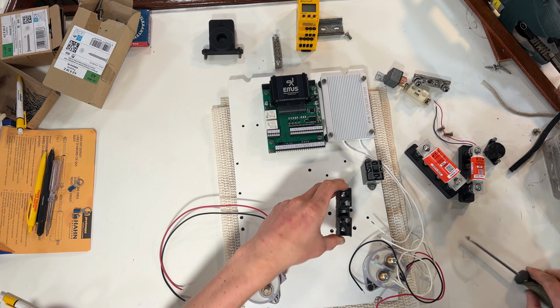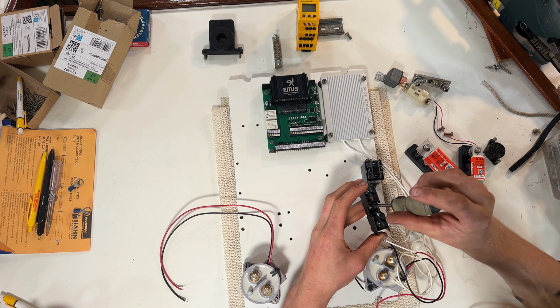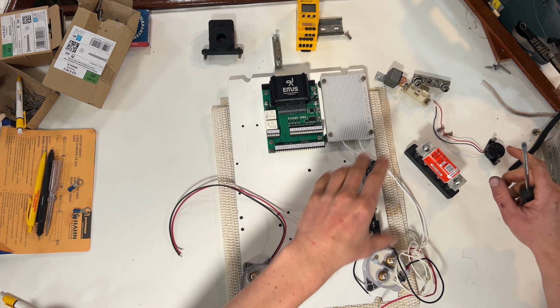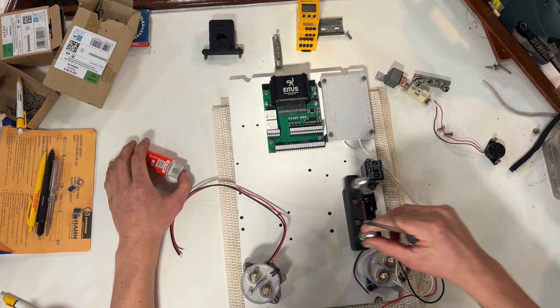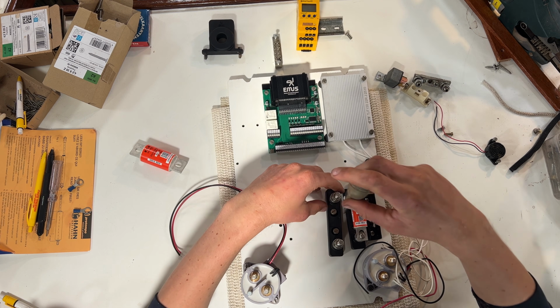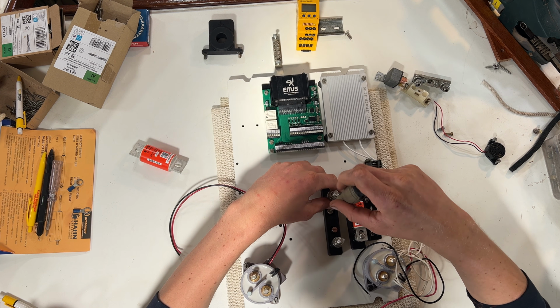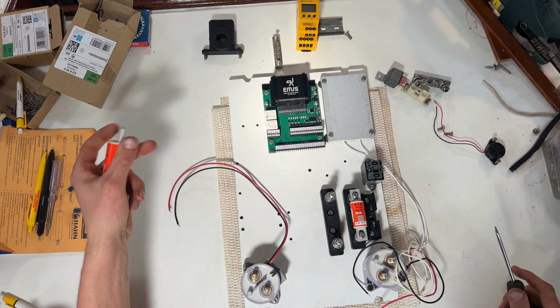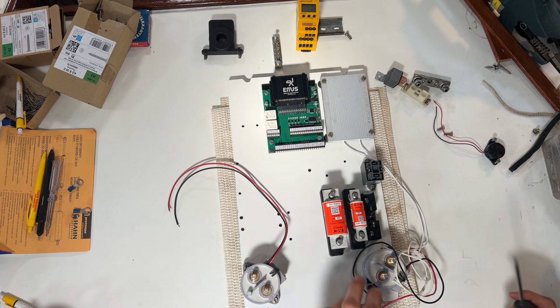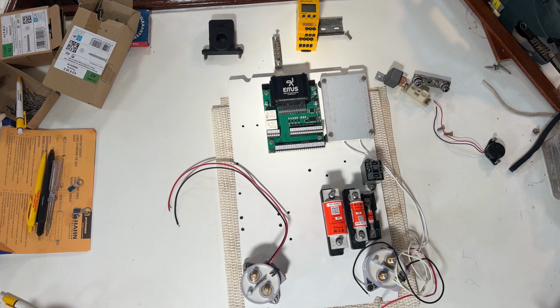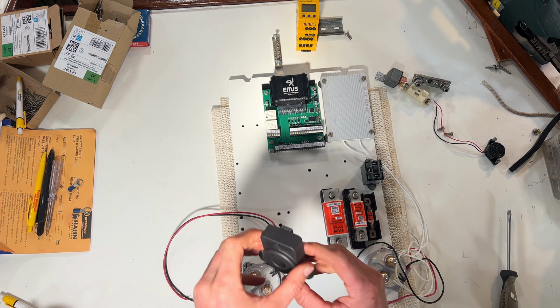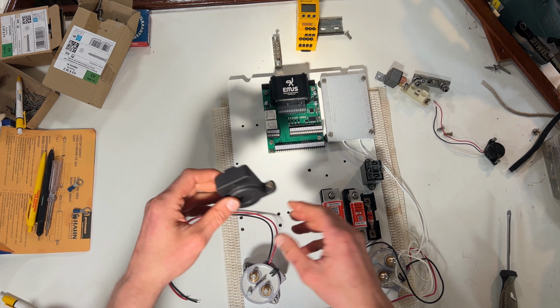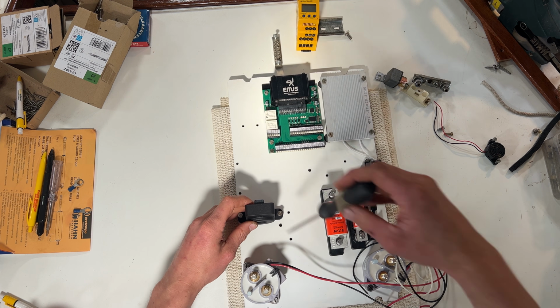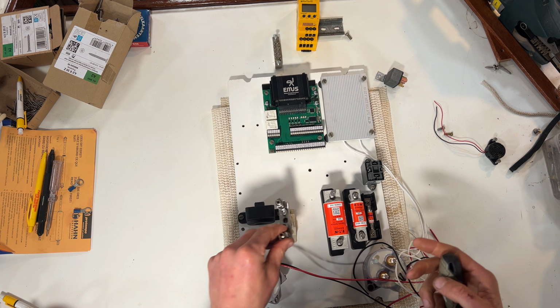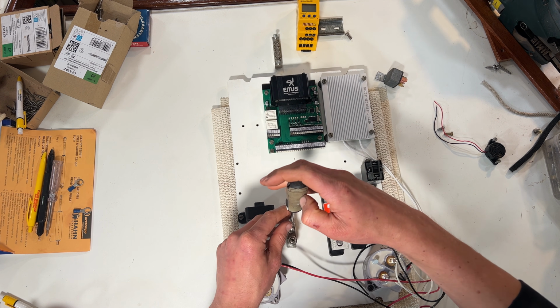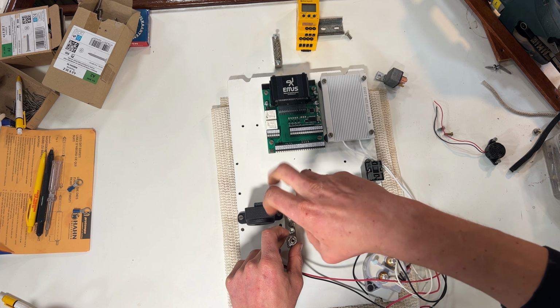Down the positive line we have 3 fuses, one for the Tesla drive unit, one for the 3-phase charger and one for the single-phase charger. The only fuse that is not in this cabinet is the main pack fuse. That one lives inside the battery enclosure, which we'll get to later. In the negative line, after the main contactor, we have the current sensor, which talks directly to the BMS, so it knows exactly what the pack is doing. Right after that, we have a central negative bus bar where the line splits towards the 3 downstream components.